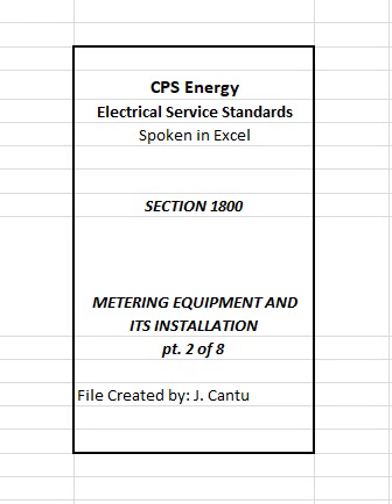A. Customer's calculated load and service conductor criteria. The use of instrument transformer rated metering equipment will be determined by CPS Energy and will depend on the calculated load to be supplied and the service conductors to be installed. Customer shall determine calculated load and service conductor sizes in accordance with the NEC, refer to definition of calculated load. Where customer's calculated load exceeds the values outlined in Table 1802, instrument transformer rated metering equipment must be installed. Where customer's service conductor size exceeds the maximum allowable specifications outlined in Figure 1801 or Figure 1802 for self-contained meter sockets, instrument transformer rated metering equipment must be installed.